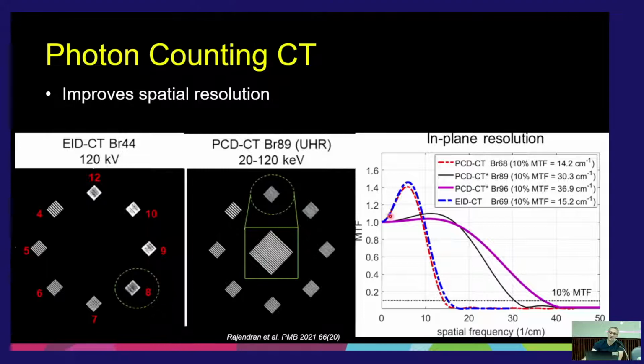In fact, if you do a simple calculation doing MTF, which we talked about yesterday, traditional single energies would drop off around 10 or so, maybe 15 line pairs per centimeter. Now with photon counting, you have so much resolution. You basically have equal contrast for double the resolution. And that's why you can see all the way down here, whereas these are all just kind of averaged together.